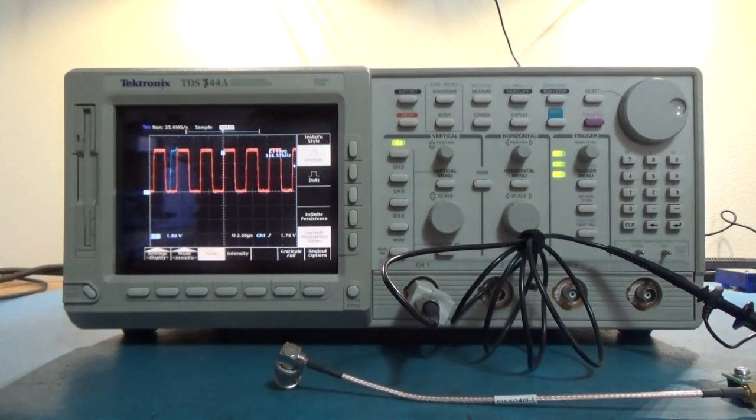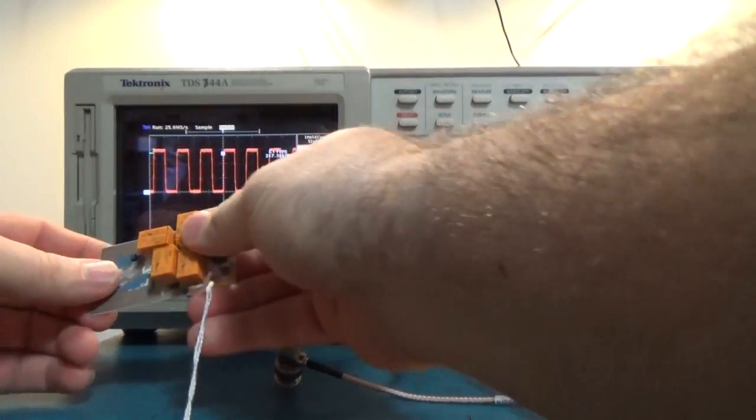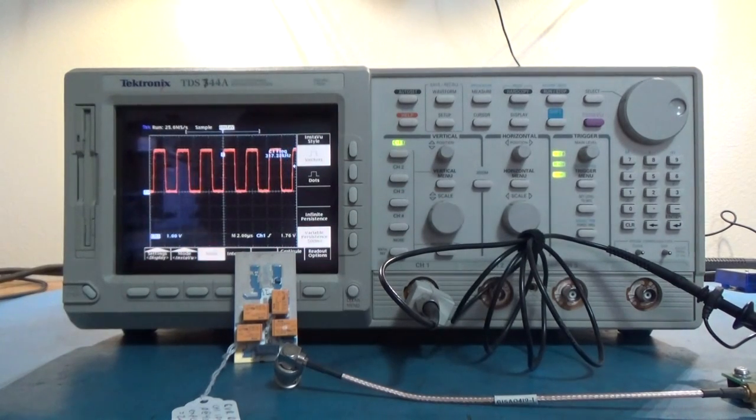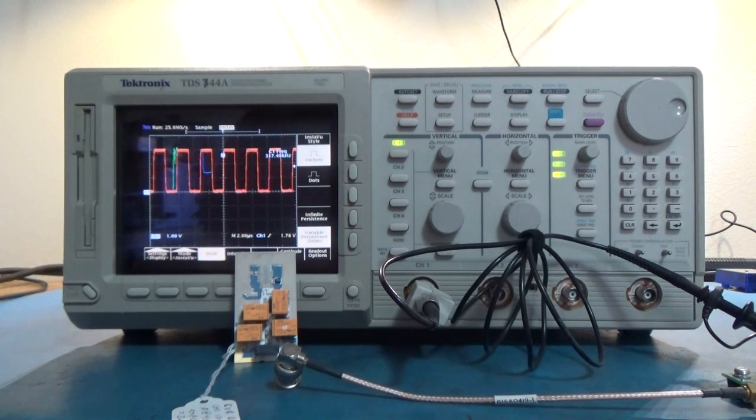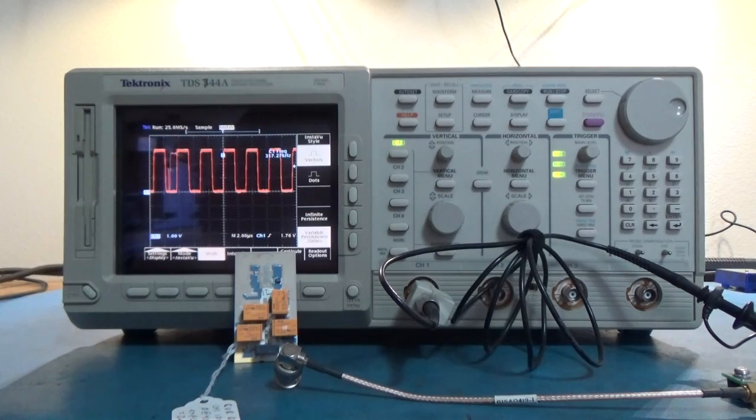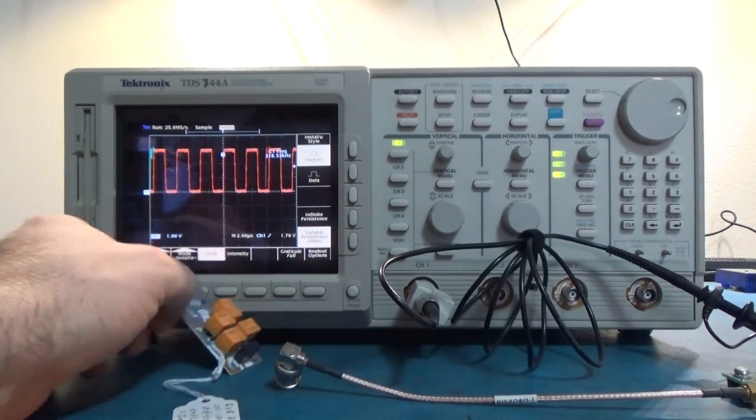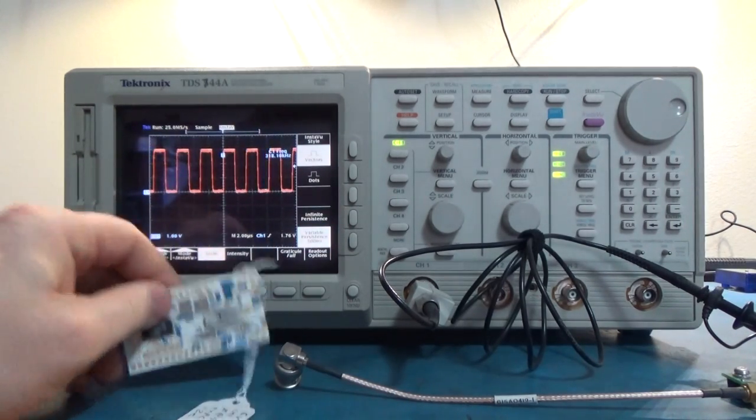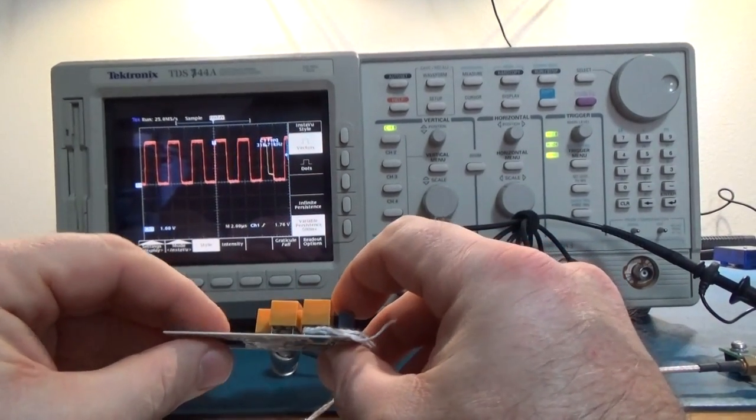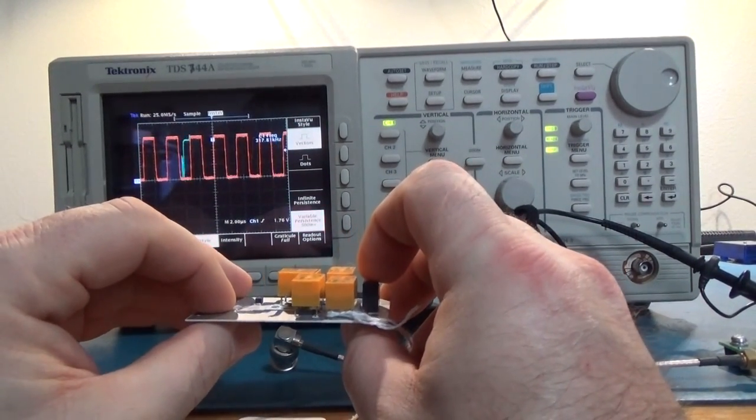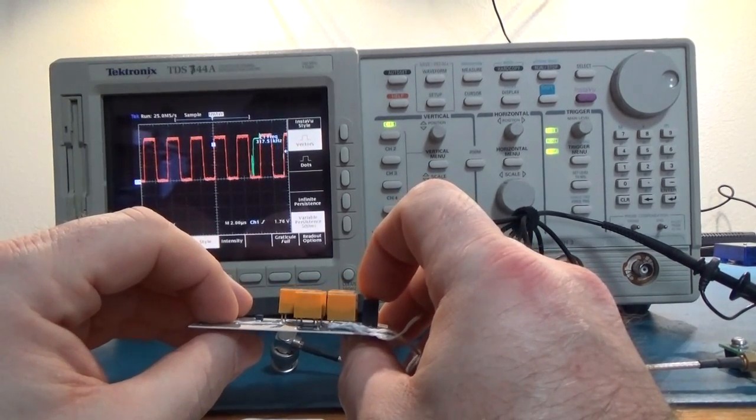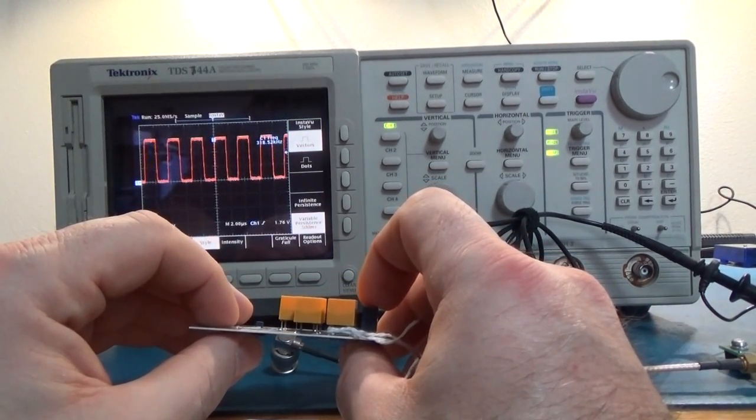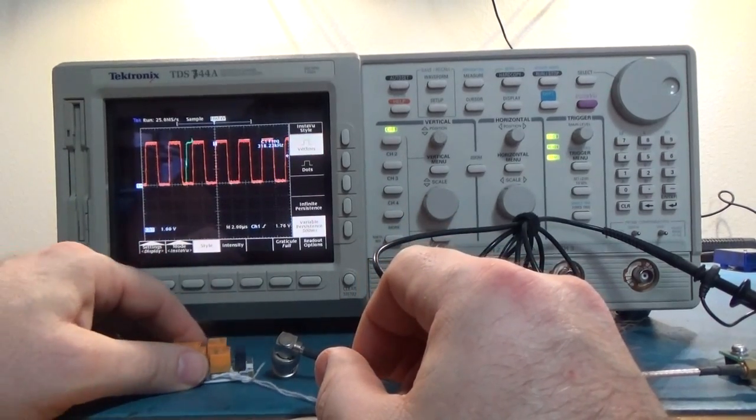If you find the attenuator that's gone bad on these, the attenuators look like that. They're a little ceramic PC board. And they shatter if the scope gets dropped hard enough. The other thing that fails on them is the solder at the feet will sometimes fail. You can't see it, you can't tell, but you can take a soldering iron and you just reheat it and it works fine.